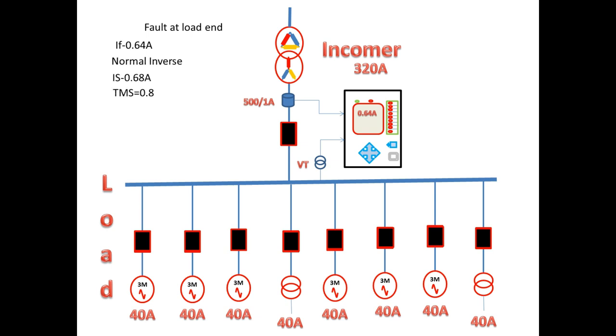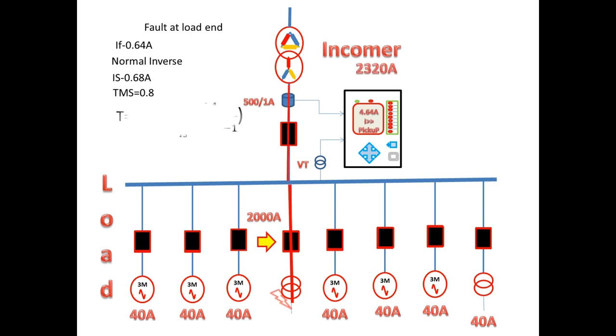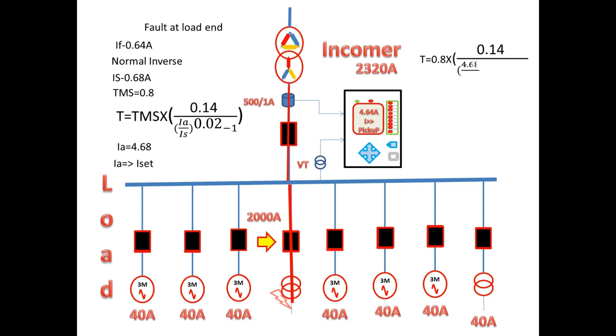The curve selected was normal inverse. The ISET is 0.68 and TMS is 0.8. Now we consider a suddenly heavy fault occurring on one of the feeder transformers. Due to this fault the fault current taken is 2000A. The actual current on the secondary due to this fault and load current is 4.68A, which is greater than ISET, so the relay will start to pick up. Substituting all values into the formula, we get a trip time of 2.8 seconds. The incomer gives a chance to the fault feeder to trip first, but if it is not tripping, the trip time is 2.8 seconds.